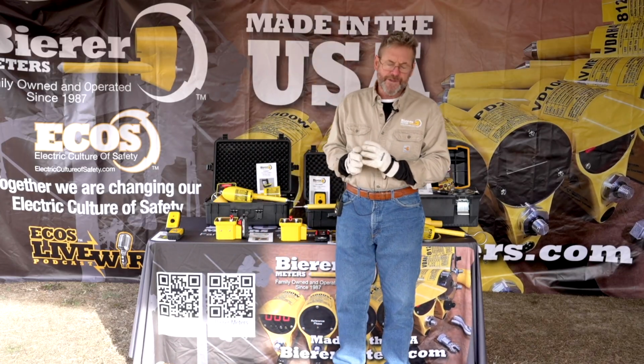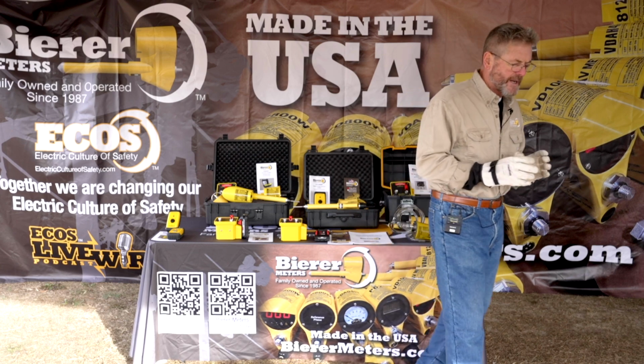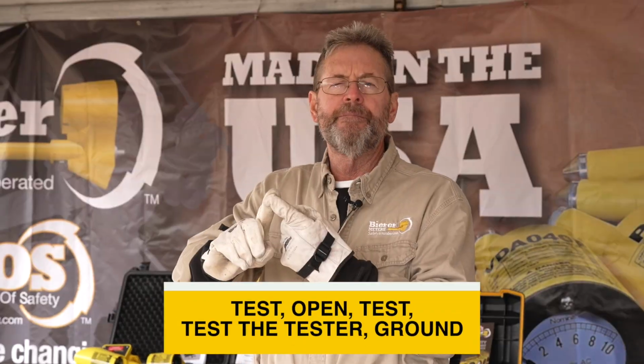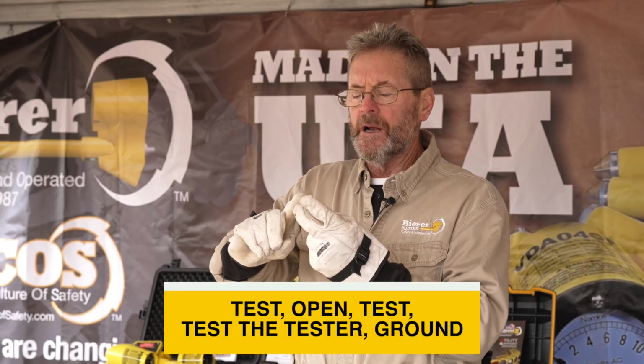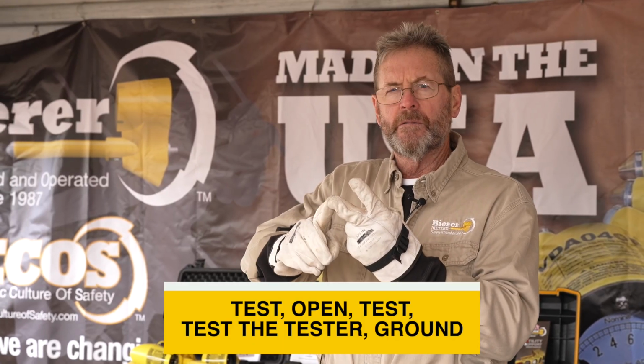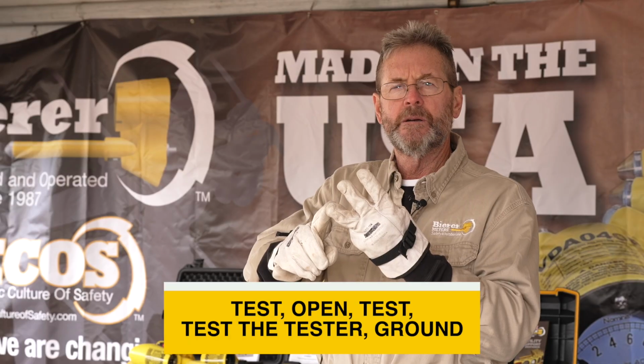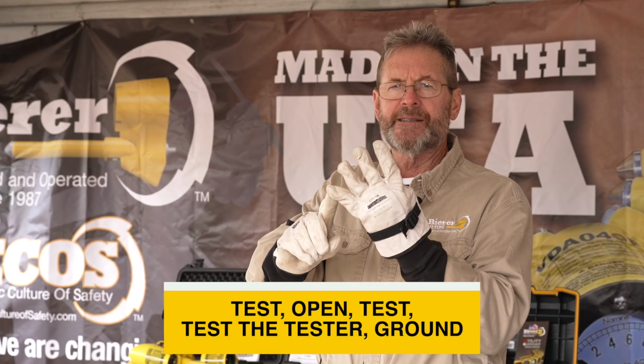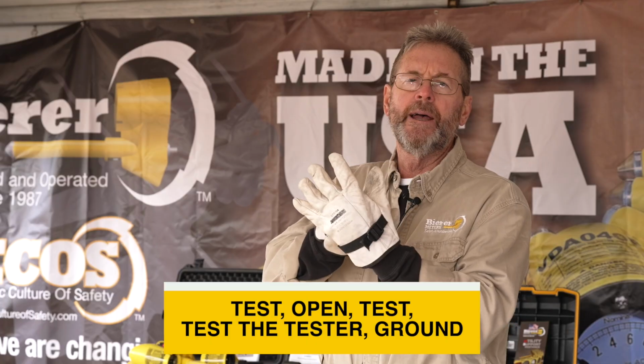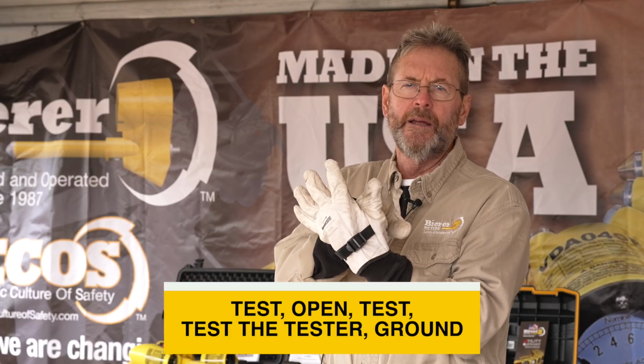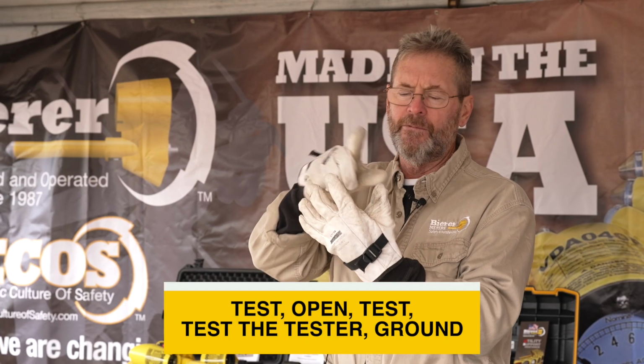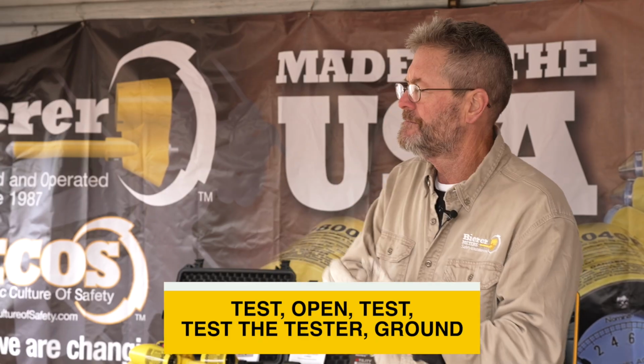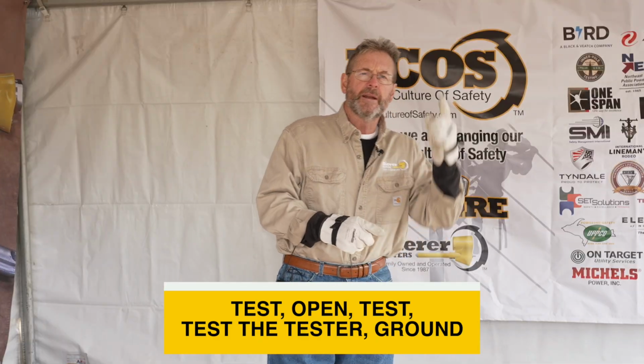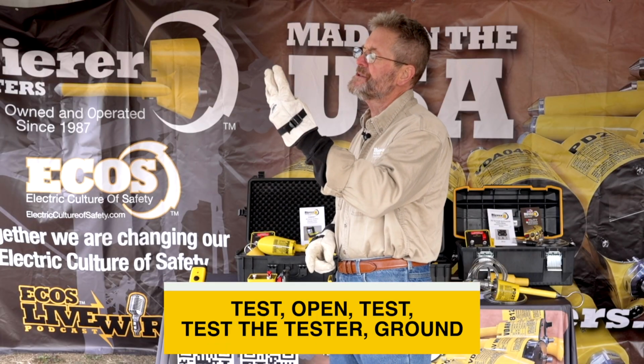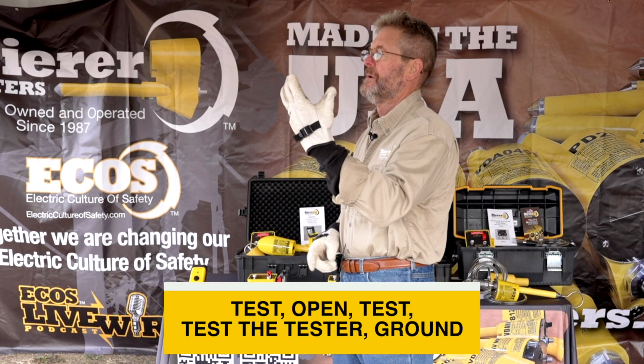Here are the steps, and a lot of utilities and contractors are going to this nowadays. We're going to go live, we're going to test, we're going to de-energize, then we're going to test, then test the tester, then ground. Once we do that, we've got our lockout, tag out, and we've got our clearance. So we always want to do those steps: test, open, test, test the tester, ground—every single time.